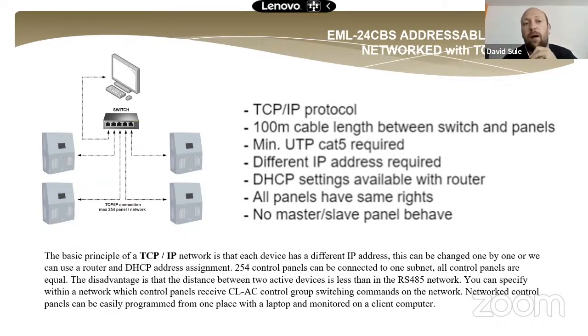So when we connect our programming laptop to the network switch, we can very quickly read all of the IP addresses of the panels. We can connect simultaneously all of the panels into the programming software, and we can make separate groups, and we can program all of the AC control, sub-DB monitoring, and device control on the other panels.